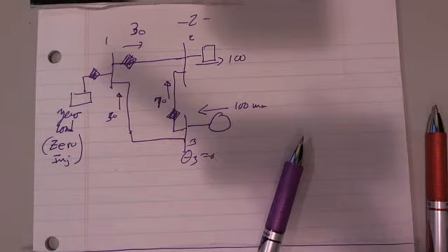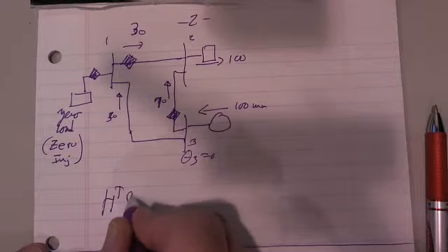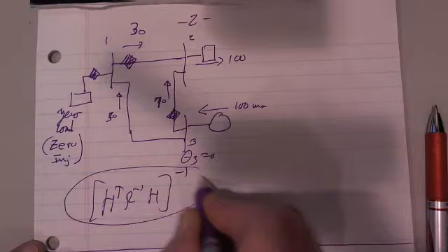What on earth do you have zero injection for, but why put the bus there? Well, that's a good question. You may put a bus there because you're going to bring one line in and have two lines going out, but you have no load or generation there. So it's still zero injection. And two things can come up. If you have a zero injection bus, when you solve it with this matrix, H transpose R inverse H, inverse, it is nearly singular.